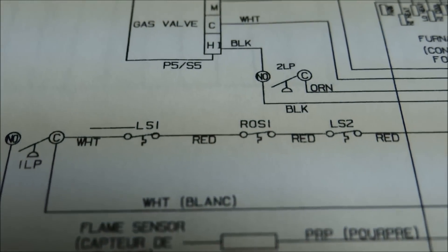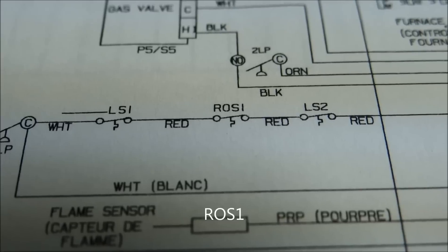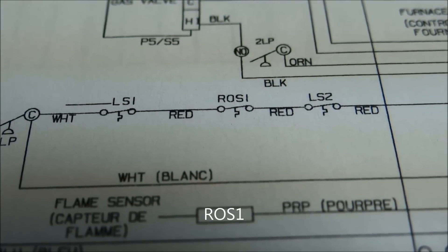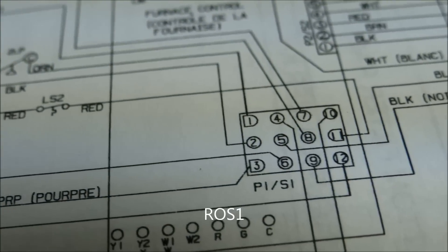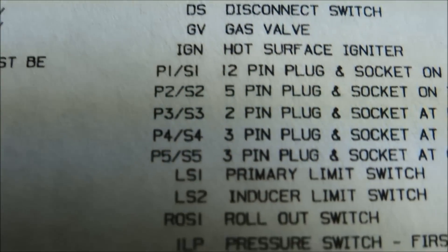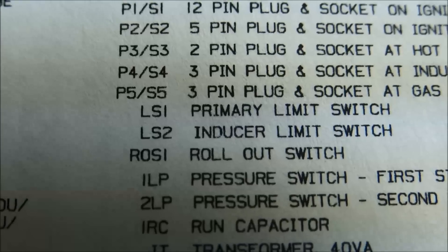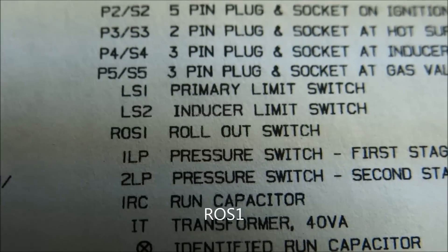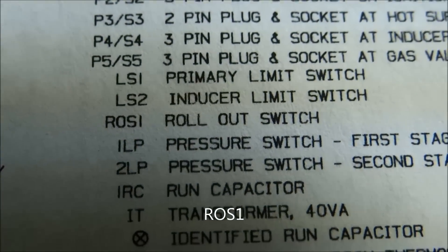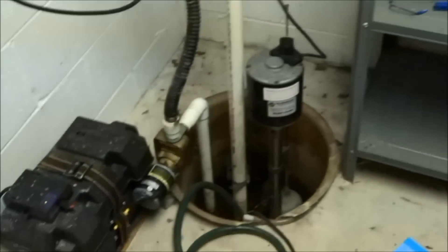I don't know if you can see this, but LS1, ROSI, and LS2 are all three in series, and then they go to this plug. If you look at the legend: LS1 is primary limit switch, LS2 is inducer limit switch, and ROSI is rollout switch. So one of those three is the problem, evidently.